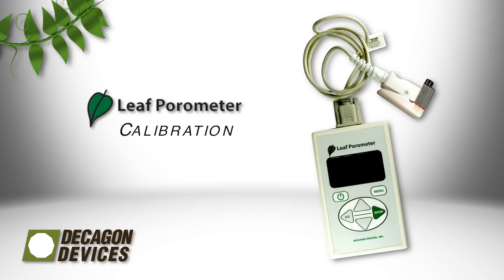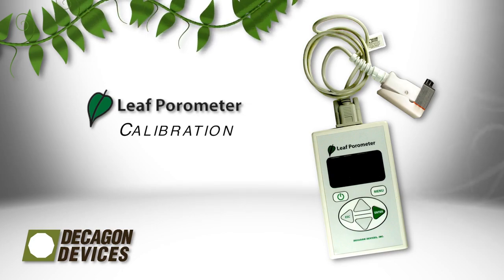The best way to ensure accurate conductance measurements is to calibrate the porometer before taking measurements. We recommend that the porometer be calibrated every day that it is used or every time it is used under a different set of environmental conditions. It is especially important to recalibrate the porometer after you install the desiccant chamber.